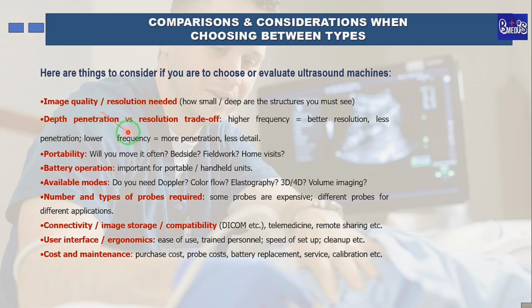Then the next thing is depth penetration versus resolution trade-off. Here we are talking of the depth such a probe can penetrate, which has a lot to do with frequency. Higher frequency equals better resolution but less penetration, and lower frequency gives more penetration but less detail. So these are the trade-offs you need to look at. Then portability. When you are faced with cases that will require mobility, moving from one place to the other, then you may have to go for the mobile unit, which is more ideal for that purpose. In portability, will you move it often, bedside, field work, home visit? These are questions you need to answer. If your work may require all of these movements, then a mobile unit will be better off.